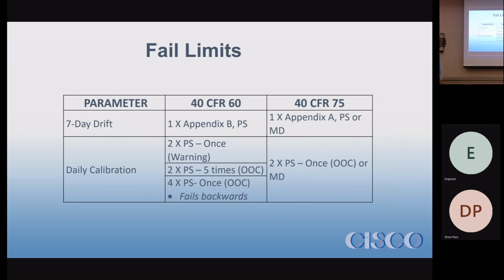Fail limits for 7-day drift. For 7-day drift, for both 60 and 75, it's one times the performance spec. Part 75 gives you an option of a mean difference. We'll get to that in the next slides. For daily calibrations, you get 2 times the performance spec. If you fail 2 times the performance spec 5 days in a row, then the data becomes invalid going forward. So the next hour after that 5th day, you start invalidating forward. Similar with Part 75, as soon as you fail a calibration, you invalidate forward.